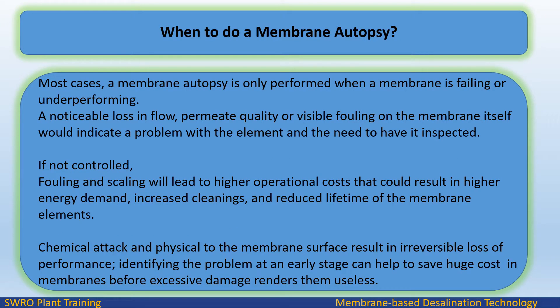When to do a membrane autopsy? In most cases, a membrane autopsy is only performed when a membrane is failing or underperforming. A noticeable loss in flow, permeate quality, or visible fouling on the membrane itself would indicate a problem. If not controlled, fouling and scaling will lead to higher operational costs, higher energy demand, increased cleanings, and reduced lifetime of the membrane elements. Chemical attack and physical damage to the membrane surface result in irreversible loss of performance.